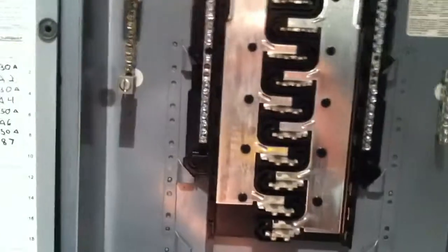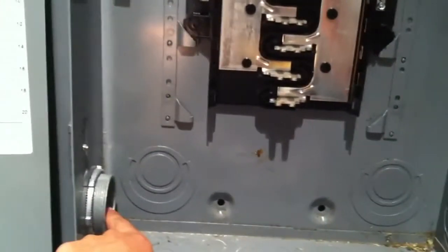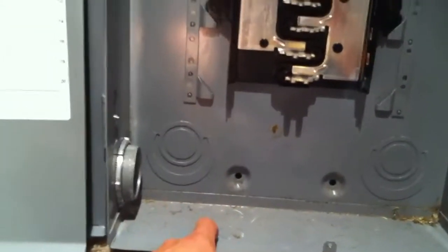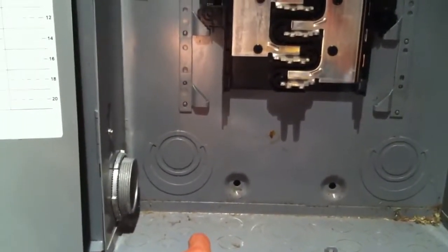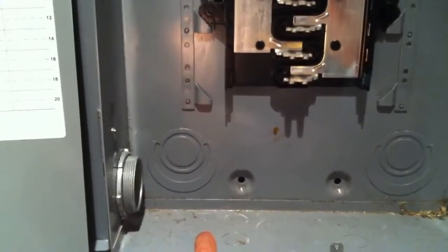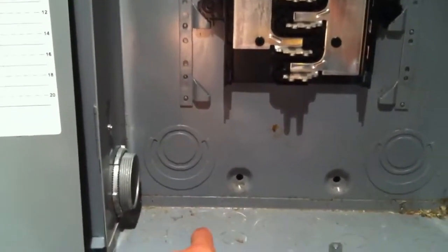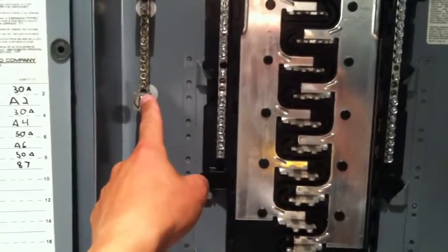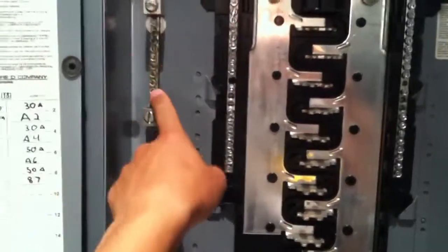Usually the ground is a big bare copper cable that comes in, usually from the bottom, going to a steel rod in the ground, literally going to the ground. It's a big copper wire, and it'll go into a ground strip like this on the side, or into your neutral strip if it's the main panel.